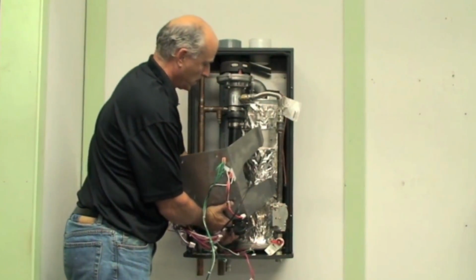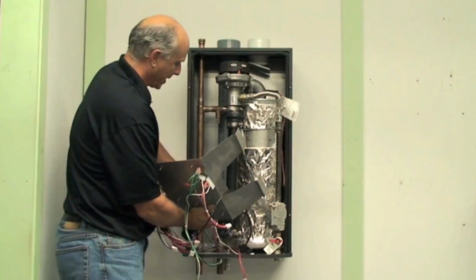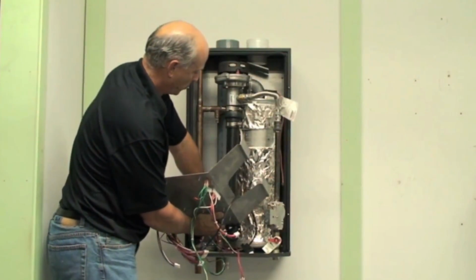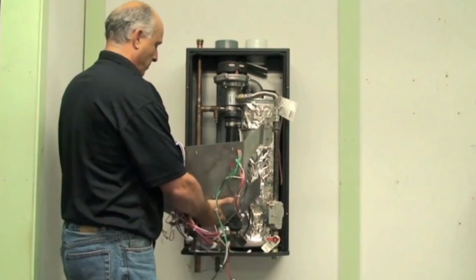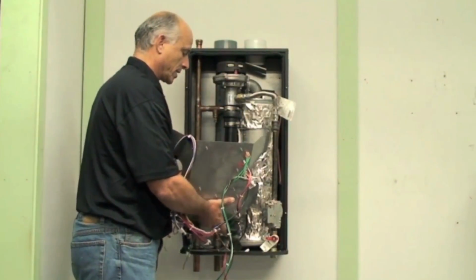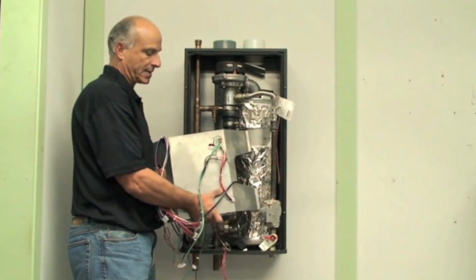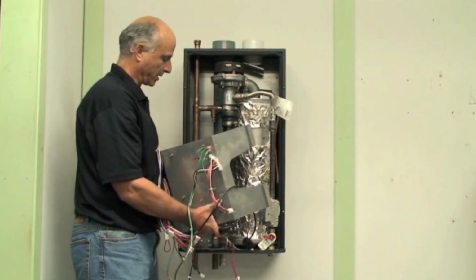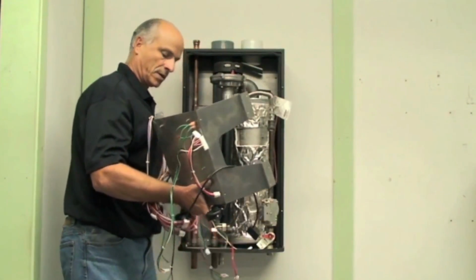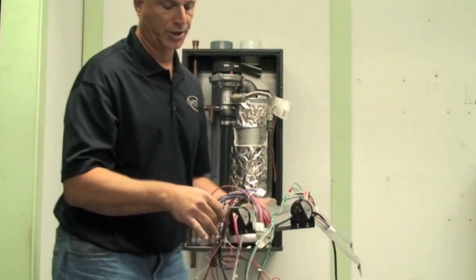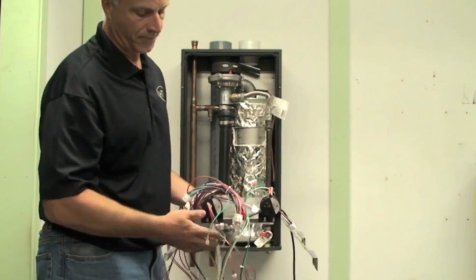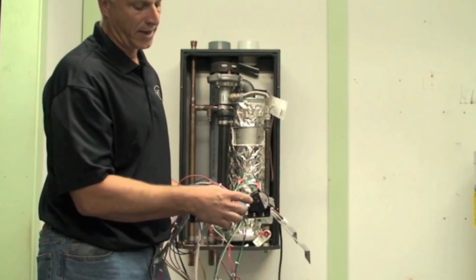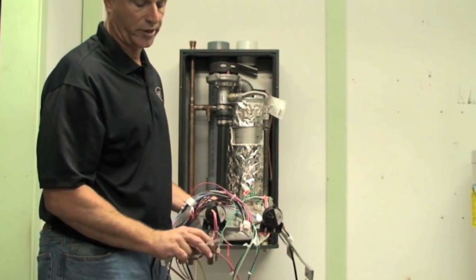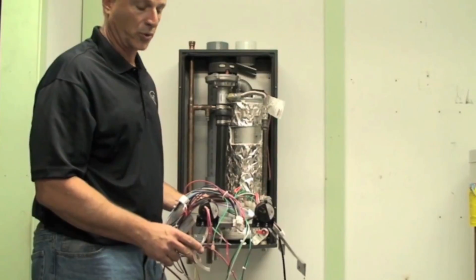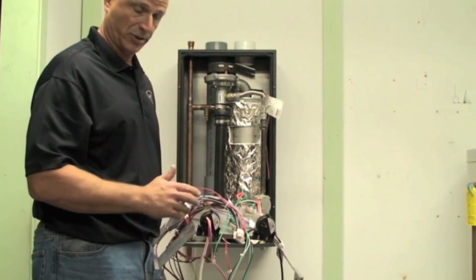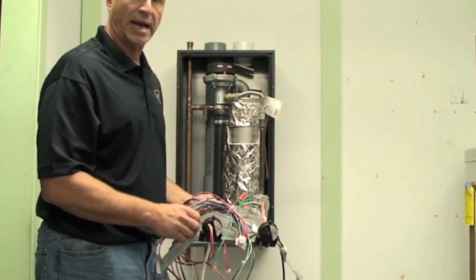Okay, I got one more connection I got to take out, and I just got to pull my hose off of my flue, and then I just got to disconnect. The last thing I got to disconnect is my condensate blockage switch. And then it comes completely out. And you can see, you got your two switches here. One of them is going to be for the block vent, and the other switch is going to be for your condensate. So if the condensate starts to back up and something's clogged, the switch will activate.